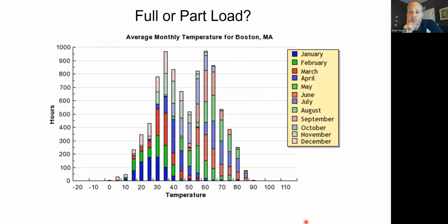One of the nice things about variable refrigerant flow is we vary the amount of refrigerant. So we vary the capacity control. So everything's going to be inverter driven. Well, I shouldn't say everything. Almost everything's inverter driven. And as you know, we have different needs based on the time of year, right?